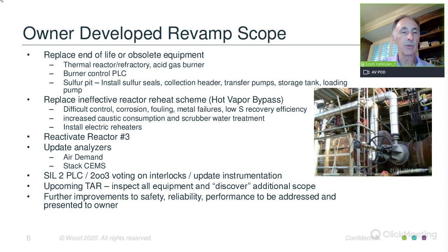And then another goal of the project to increase its reliability and stability is replacement of the control PLC, and to institute 2 out of 3 voting on many of the critical instruments. There was also a turnaround that was coming up soon after the project started, which would entail an inspection of all the equipment, in which there could be some additional scope identified. And the client was also looking for recommendations for additional improvements to the safety, reliability, and performance.